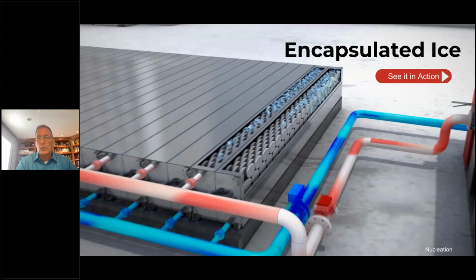If we pipe it up to pre-cool the existing chiller system in the building, those chillers, when they sense that water coming back through a heat exchanger in the middle—I'll show pictures—they sense they're fully satisfied and just shut off. You can automate it through controls if you want, but the more elegant way is to just put a heat exchanger in the middle and pre-cool the chillers.